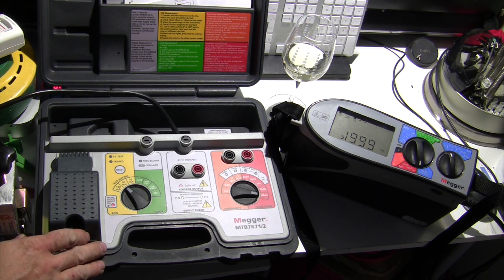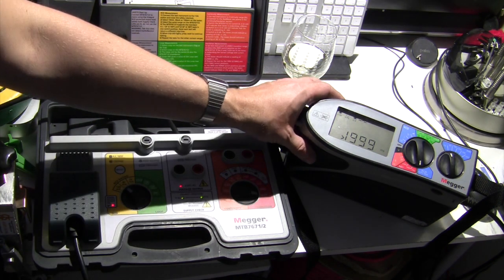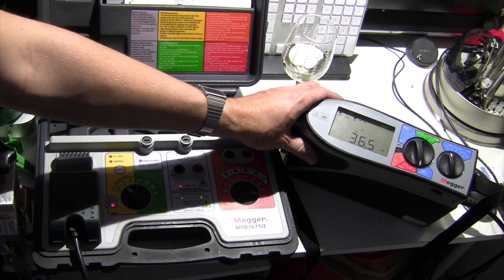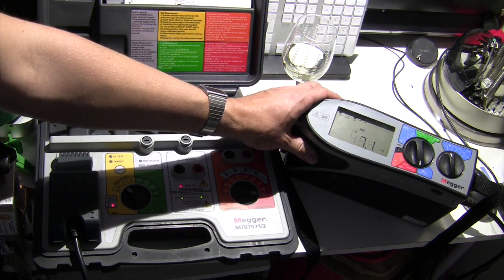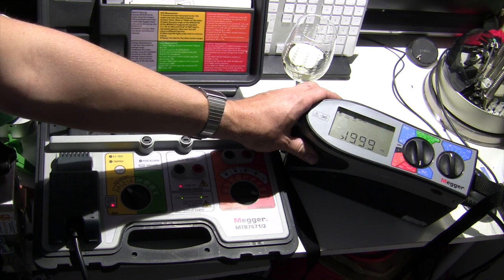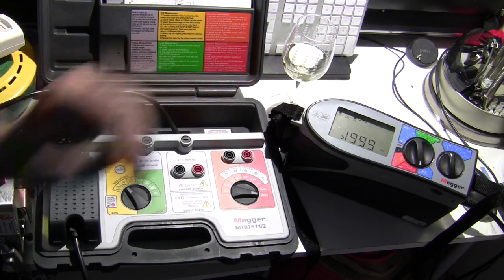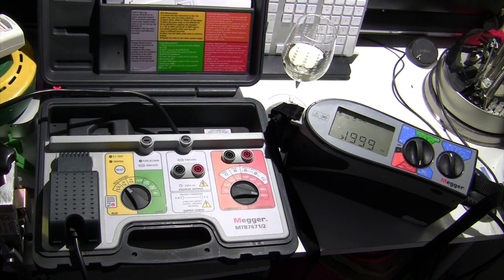So that's the RCD testing complete, and just to say, if you're not familiar with the Megger, once you've done an auto test on the RCD, you can press the red button there to cycle through the 5 numbers if you haven't already noted them down, so that works quite well. Dead simple. Okay, now we're going to move on to the loop testing.